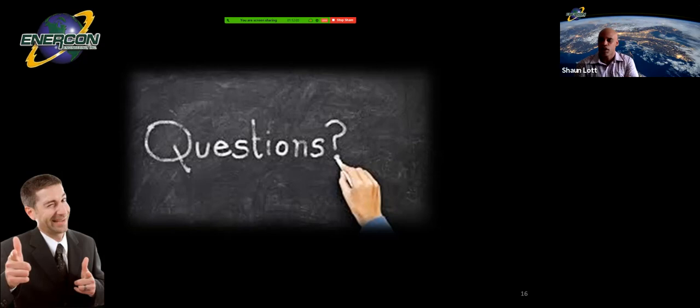It's tied to testing the effectiveness of the EMI shielding. So is there a way that you can simulate an EMI or EMP source to do the testing? You can. There are signal generators that you can use. Basically, I ran through it pretty quick in terms of our previous testing. You would use a signal generator inside the enclosure. That's one of the specialty pieces of equipment that I was talking about.